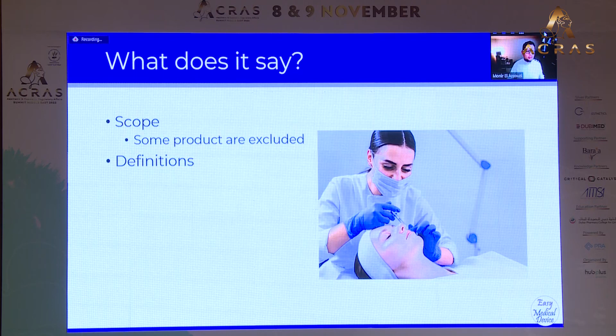We also have an important section, risk management, which specifically tells you which risks you have to look at. They have taken all the categories one by one, checked what the risks can be for each category, and put that directly inside. So your risk management documentation must also include those risks.